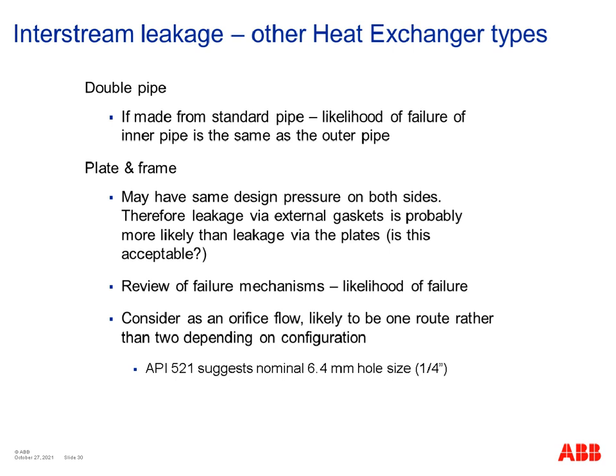It's a bit vague. So the EI guide suggests that for a printed circuit heat exchanger, the flow through one channel could be used to determine the relief rate. For plate and frame exchangers, an area of 1 millimeter squared could be used for approximating a failure due to corrosion, or 10 millimeters squared for the case of a fatigue crack. Please note that the relief flow calculation is still an orifice calculation, even though it may not be an orifice really you're thinking about. But there's only one hole you would consider, not two, as for the shell and tube exchanger rupture we talked about before.